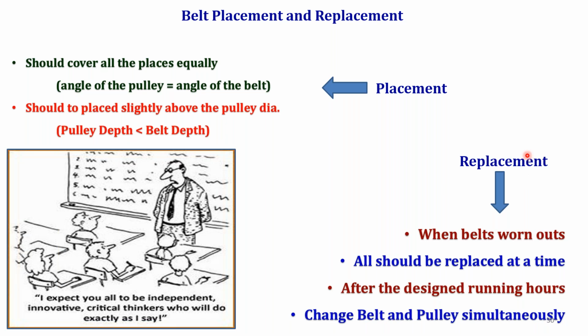Similarly, for replacement, after 1 year, after 2 years, or after a certain amount of time, when you want to replace the belt, you will check the condition of the belt, whether a burnout has happened. Suppose you have a 3 belt and 3 pulley configuration, and you found that only one belt is completely damaged. Then it is not a good practice to change that one particular belt.